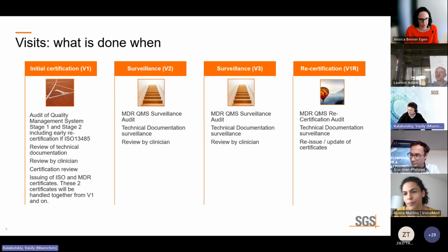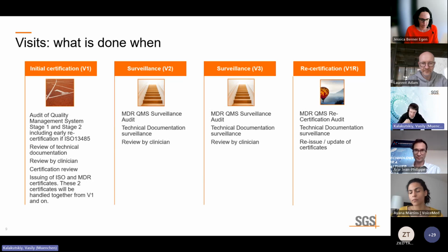Yes, it is not very often, but it happens that a manufacturer has a different view on that. The official way is, I also talk about it. But the usual way is reading the documents aloud together and finding the truth. So basically, we rely on MDCGs, the documents that are issued to support both sides, the notified body and the manufacturer. They update these documents quite extensively in recent days, and they issue new ones. And I think they are now heavier than actually the MDR.